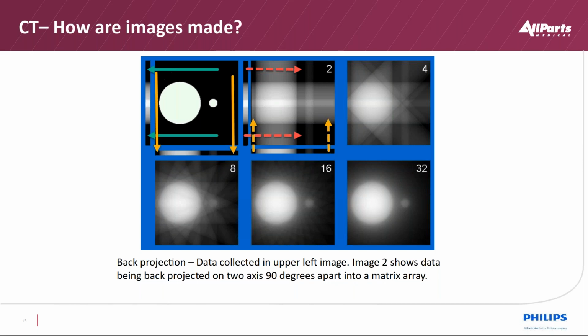And then we push those projections back over a matrix. In this case the matrix would be 512 by 512, or on newer scanners 1024 by 1024, or even 2048 by 2048. We push the data back through there, and as we get different views, we push it back from different angles, and we get an accumulated image, where it says 32 there, that closely approximates what we scanned. But if you notice, it's foggy. And the reason is the data set. As you collect more and more data, you still have rounding errors, so to speak, even though you're doing advanced math functions. When you do projections, you still have it.